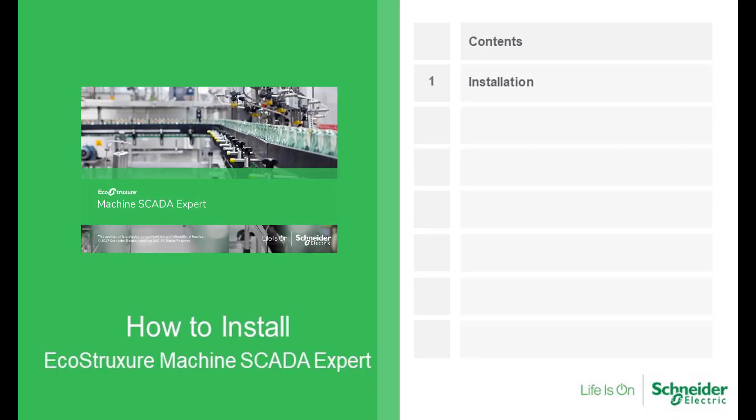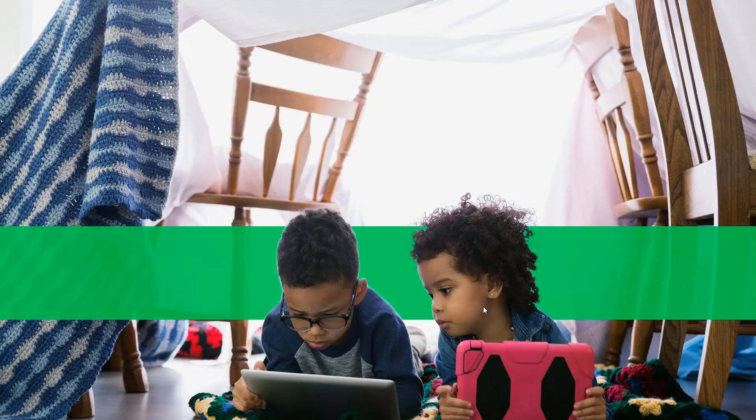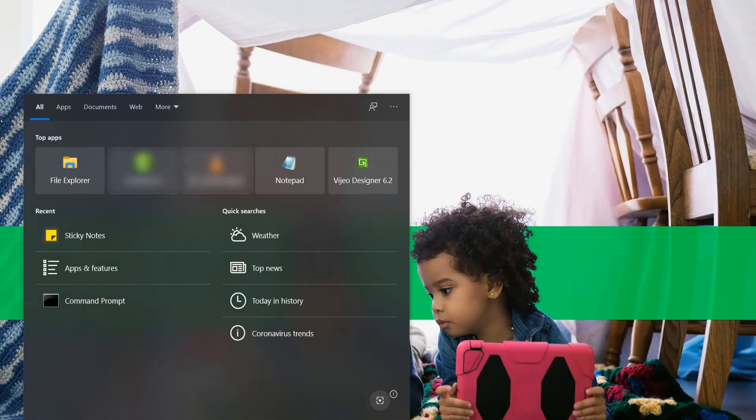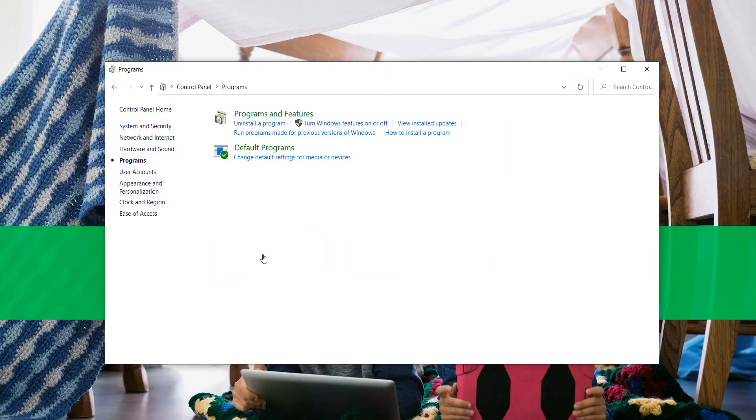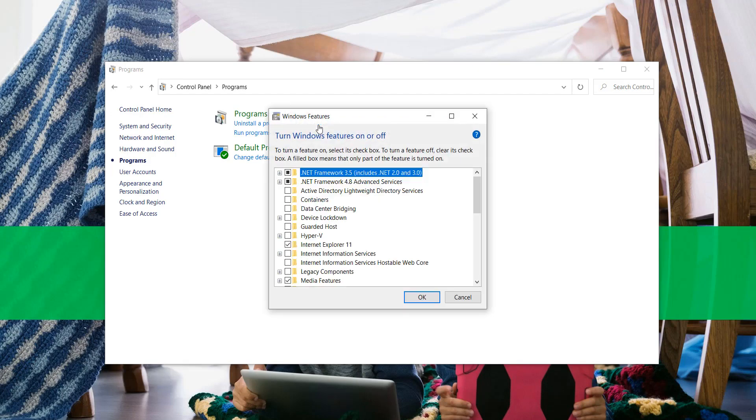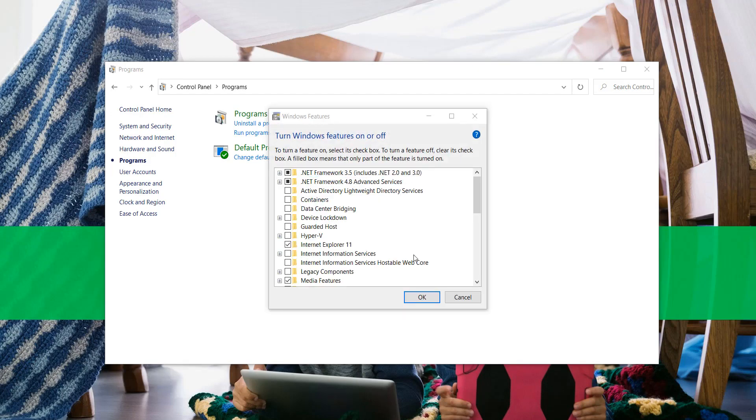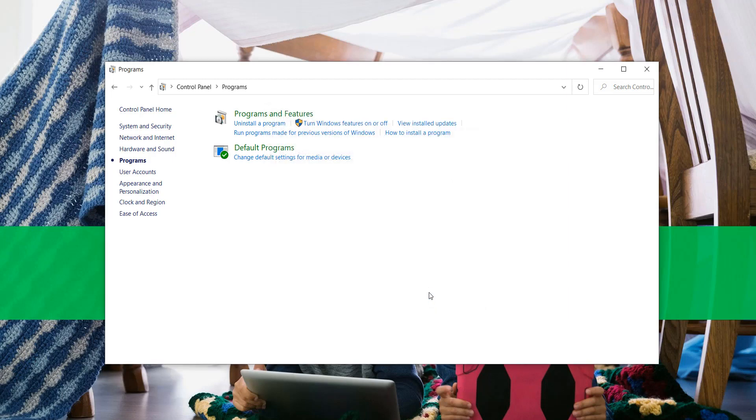This video will guide you on EcoStruxure Machine SCADA Expert installation. To install and run EcoStruxure Machine SCADA Expert, you must have both .NET Framework 3.5 and .NET Framework 4.7.2 or later installed. If in your application you want to use the industrial graphics editor that has been integrated into EcoStruxure Machine SCADA Expert from version 2020 as an option for screen design, a web server must be installed and configured.